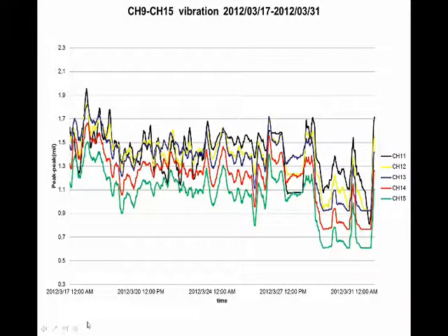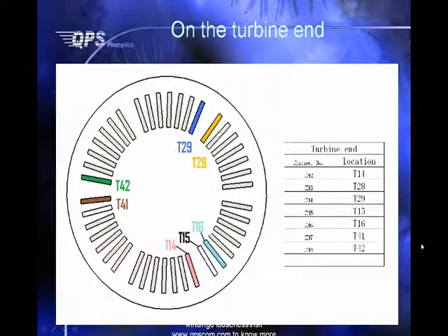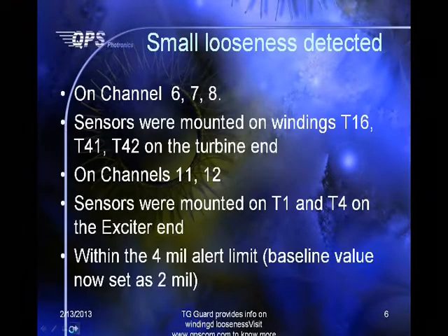Now we look at the other sensors. One of them, by the way, channel 15, is very low, and on the high side you have channels 11 and 12. If you don't mind, I'll go back to the cross section here. On the turbine end we actually installed 7 sensors, and one of them was directly attached to the copper conductor, T15. So I'd like to examine that for you, what the reading looks like, and that's channel 5. Okay, channel 5. So let's go back to the actual data.